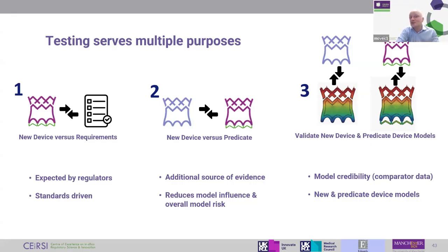So I get to start with, why do we do testing at all? In this scenario, the manufacturer would do testing for 3 distinct reasons, laid out here. Number 1, the new device will have design requirements just like any device. Those will need to be verified. That's a given, so we can set that aside. The second one is that perhaps you would do comparative bench testing. That could be used to demonstrate that the new device is expected to perform equivalently or maybe even better than the predicate device. That head-to-head testing is invaluable. It could form a really important part of a submission and an important part of that justification that I talked about earlier to reduce the trial size.